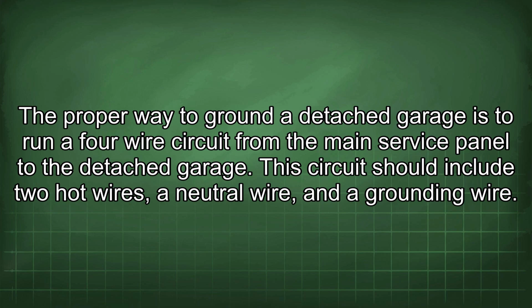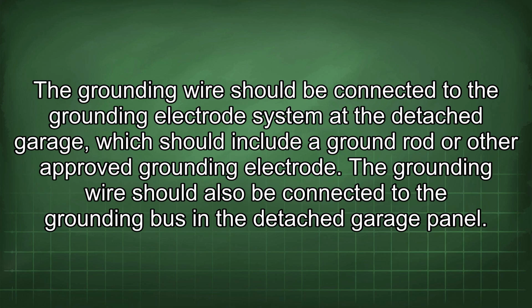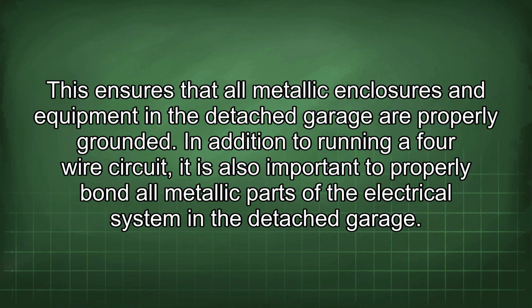This circuit should include 2 hot wires, a neutral wire, and a grounding wire. The grounding wire should be connected to the grounding electrode system at the detached garage, which should include a ground rod or other approved grounding electrode. The grounding wire should also be connected to the grounding bus in the detached garage panel. This ensures that all metallic enclosures and equipment in the detached garage are properly grounded.